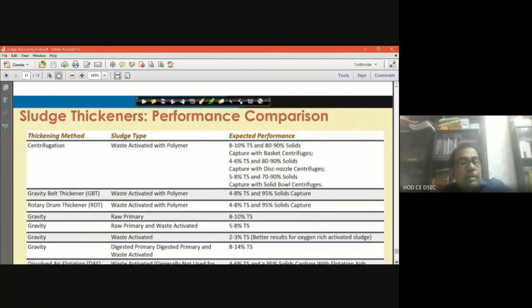Now the gravity thickening process, the raw primary sludge we can use, no doubt about this. The expected performance is 8 to 10% TS. So primary sedimentation, primary sludge we can consider. Initially we told you that dry solid is 4%, so that can be improved to 8%, that is double.